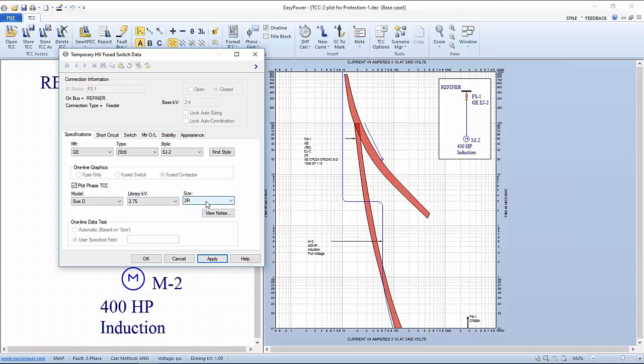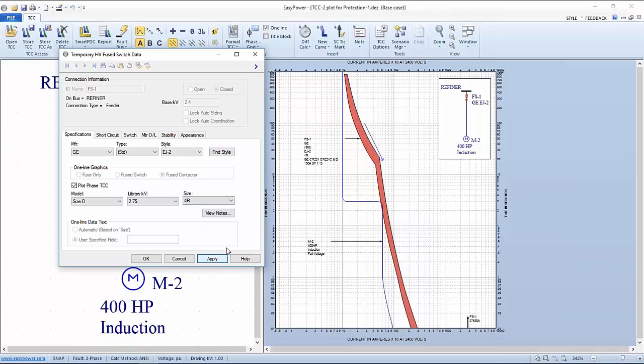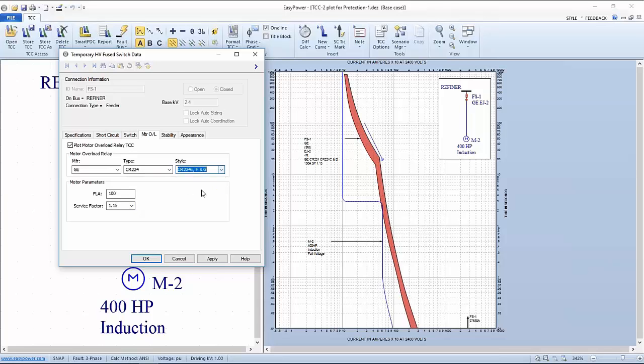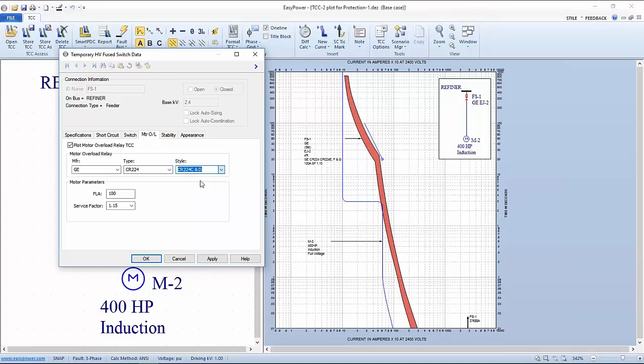What this amounts to is that normal operations is to the left of the thin blue line. But if the motor gets exposed to any current to the right of this short stubby curve, it could potentially suffer thermal damage. That's the function that the manufacturer wants us to pay attention to. That means if this fuse contactor is going to protect the motor, it needs to be to the right-hand side of the thin blue line and to the left-hand side of the thermal damage curve. That's what we've been able to accomplish with the way this fused contactor has been set up.